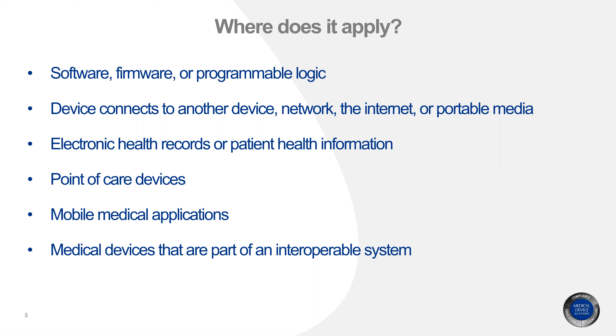Oftentimes, manufacturers think that if the device is not an implant or is non-sterile, it's free from an attack. One of the main issues is that manufacturers are not addressing cybersecurity vulnerabilities in internet of medical things devices. Some manufacturers may be slow in addressing security issues because they have fewer resources, large code bases, are driven by speed to market, are concerned about cost, or may not be aware at all. As soon as you place your device on the network, or if it has portable media or a software app, it becomes a hackable system because it has programmable logic.